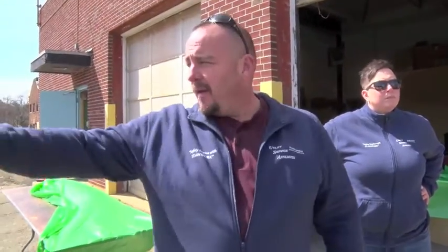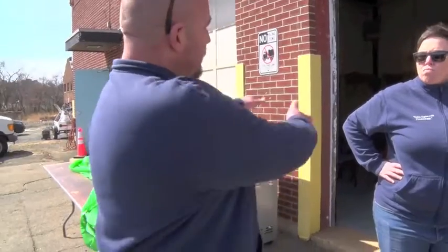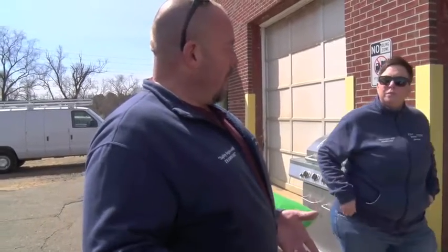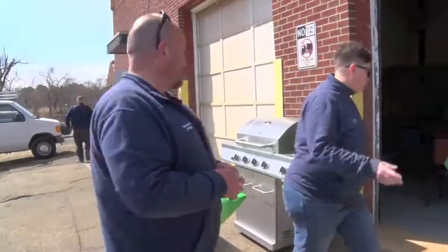This is basically the final stage after our pre-treatment at the clarifiers. The water goes over the weirs, goes through a set of piping, and comes under this garage bay into the filter bay. From that point, it gets pumped from the wet well into the filters for filtration. After that, it leaves the plant, and then there's sodium hypochlorite, which is added as post-chlorination treatment. Everybody can walk in through this way and get to see the filters.